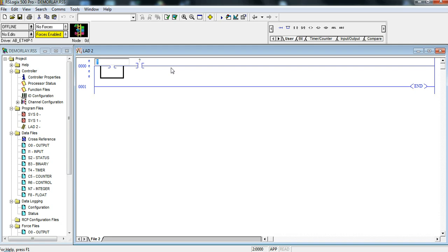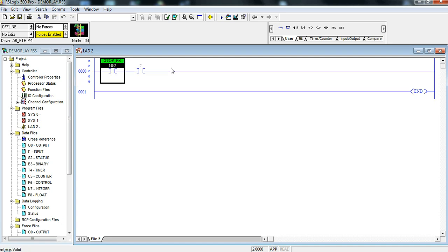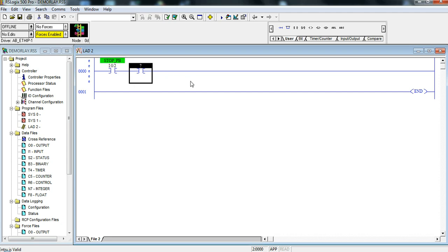What I'm going to do now is address this to where I know the stop button is wired to my PLC. On my PLC, any inputs that we use are always I so I will always start your address I colon zero. When I put the zero on there it tells me it's in slot zero and where you slash two is my stop push button. That stop push button is an input because it's an I colon and zero is slot zero and slash two tells me that it is physically wired to pin number two on the PLC.